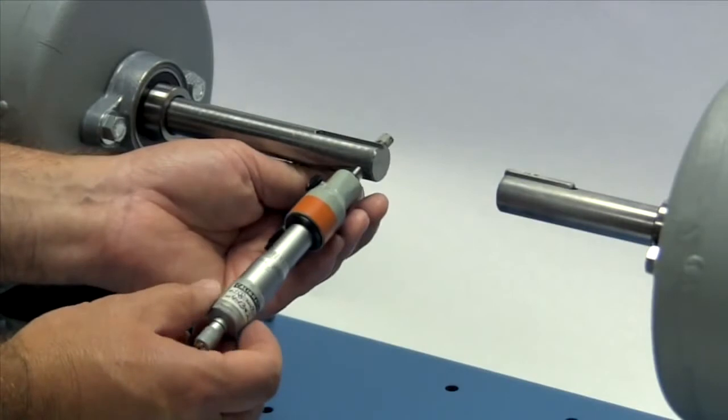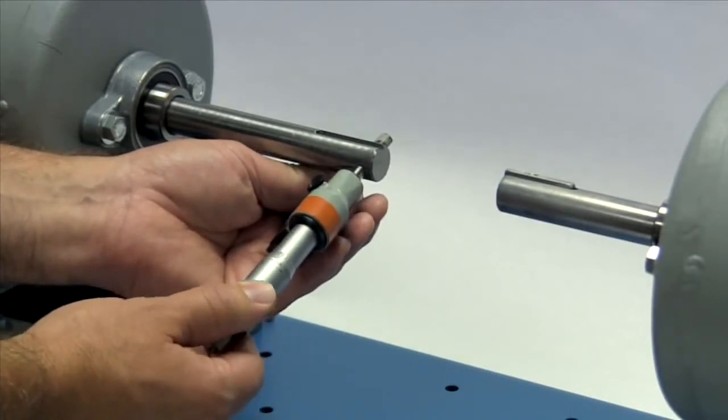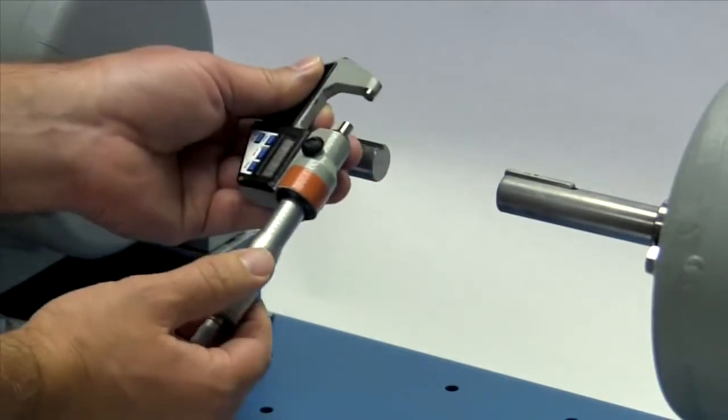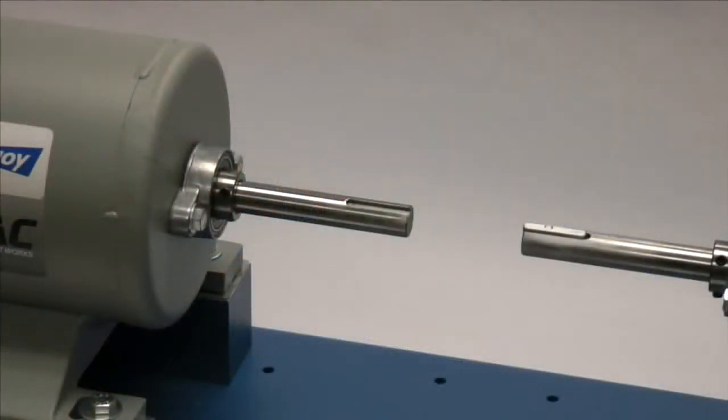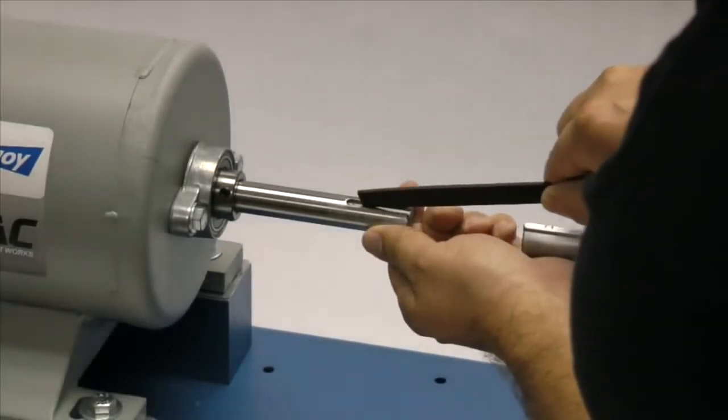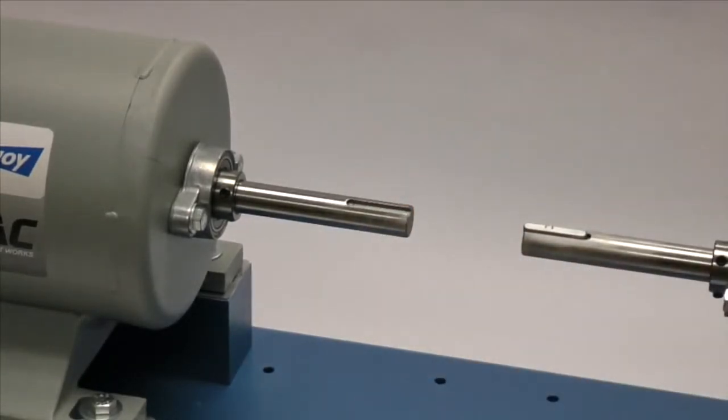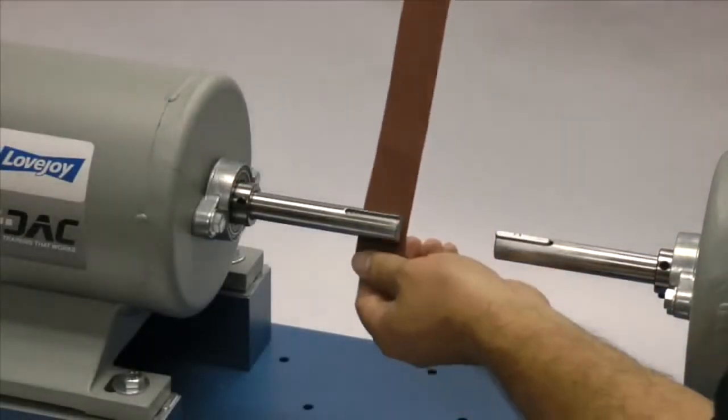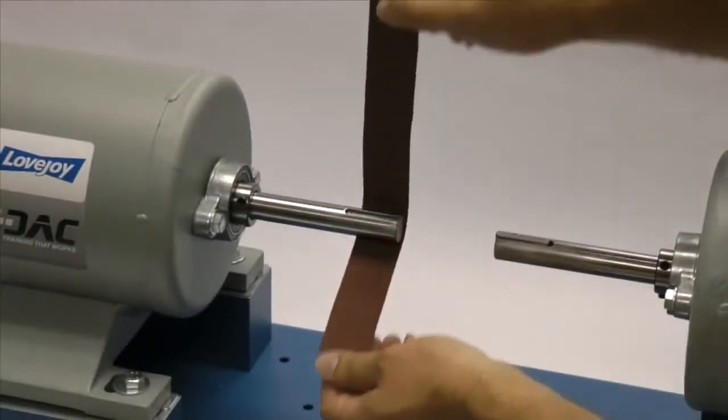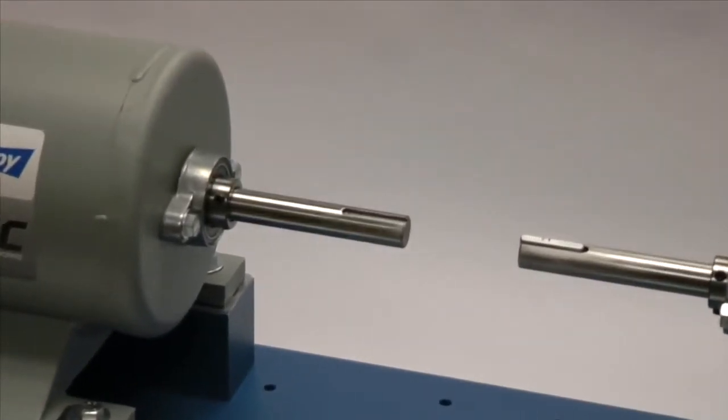If not done already, you should measure the shaft and ensure that the shaft diameter matches the coupling bore size. Then inspect the shaft and clean off any nicks or burrs from the keyway or shaft diameter. A fine tooth file can be used to clean burrs from the edge of the keyway or large dents in the shaft. The emery paper can be used to clear the shaft of rust or any fretting corrosion.